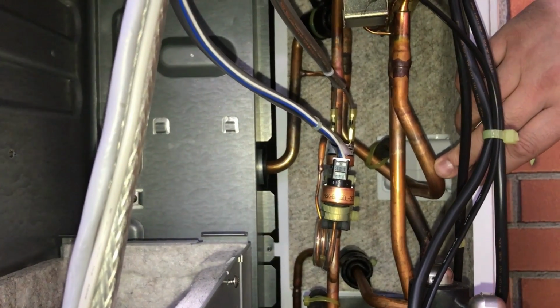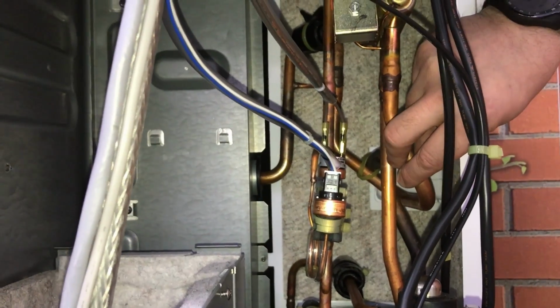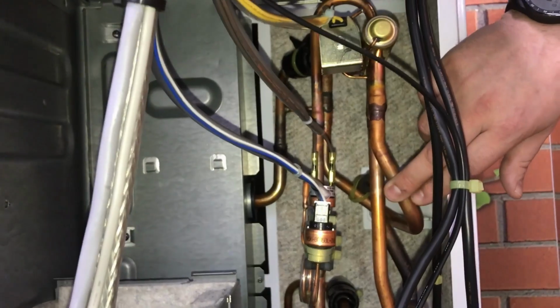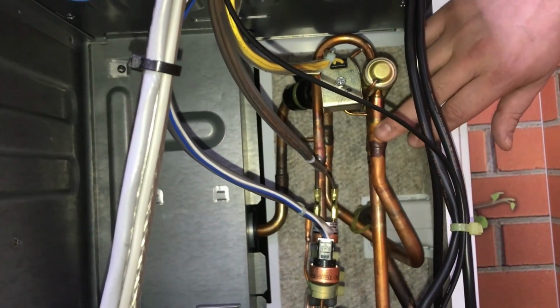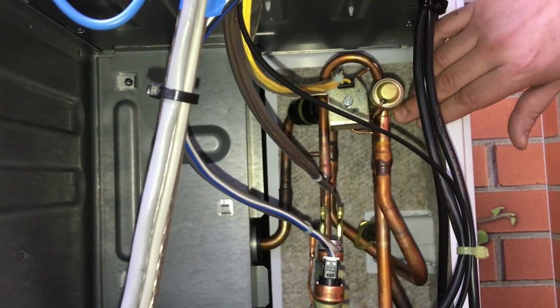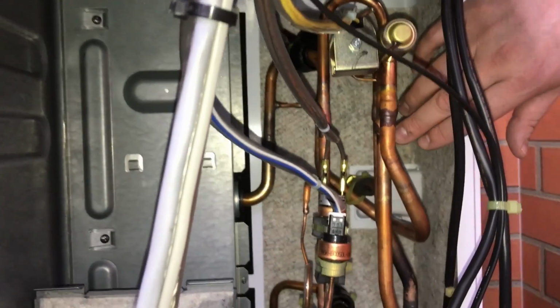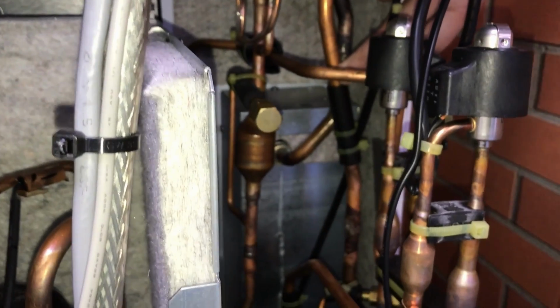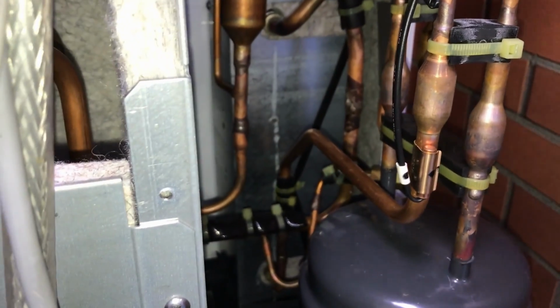There's my refrigerant pipework coming back from the coil. That's nice and cold, below the ambient temperature. Comes into that reversing valve, passes through the little U piece inside there. From there, passes back down, back into the compressor, and we start all over again. Take it from being a low pressure, back up to being a nice high pressure.